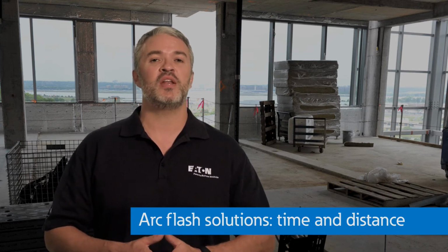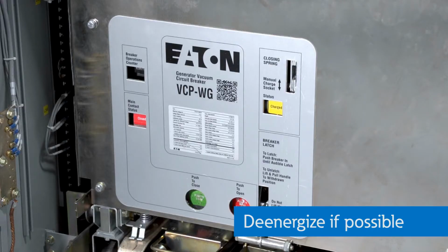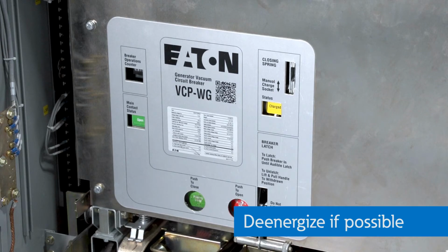There are many different arc flash solutions. Time and distance are typically the variables that we focus on to eliminate or reduce the risk of arc flash injuries or equipment damage. Of course, de-energizing your equipment is always the safest bet, but we know that isn't always possible, especially when working in healthcare environments. For arc flash solutions to try to limit how much time we would need to spend in the suit, there are newer breakers out there. There are newer methods, depending on how new the equipment is in the hospital. Many hospitals still don't have the newest, latest, and greatest protections installed. So it is important to look at every element in the system and see what the best solution is going to be for you to maintain a safe work environment, but still be able to get your work done in the most efficient manner.